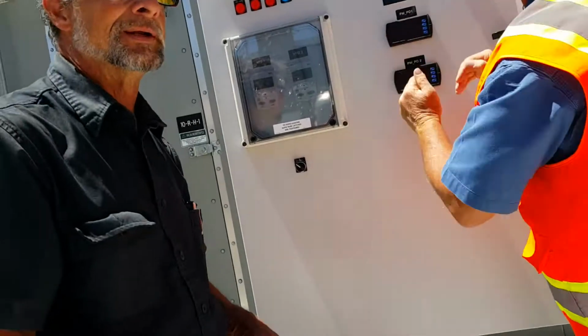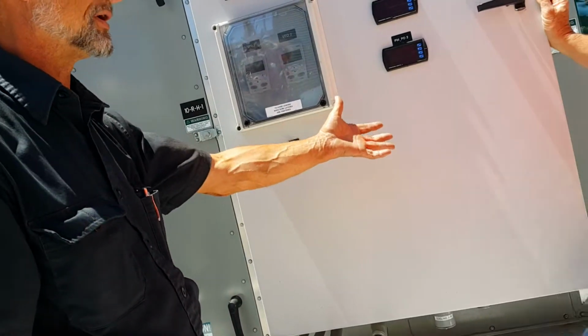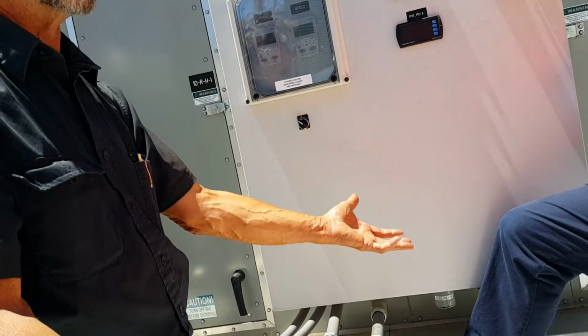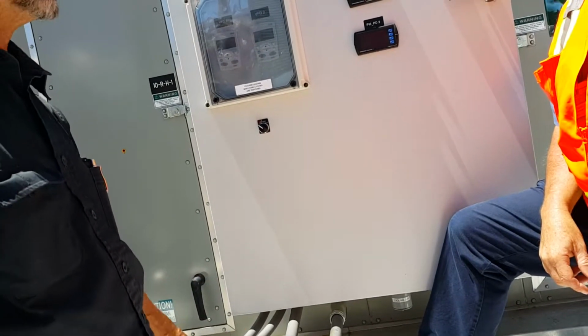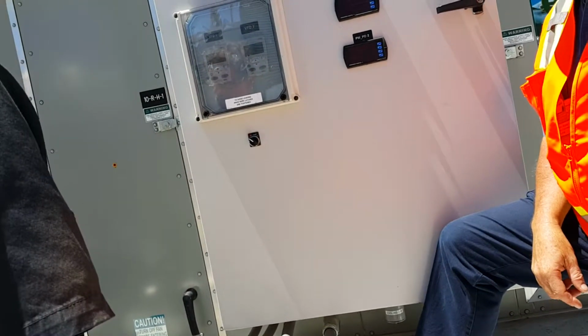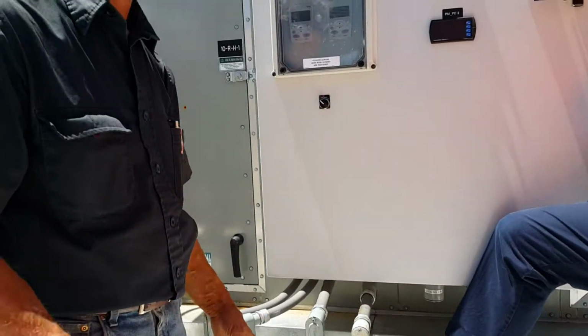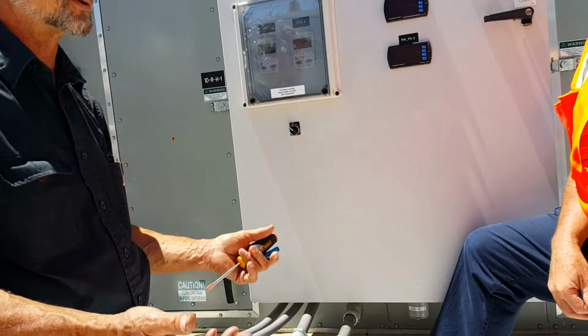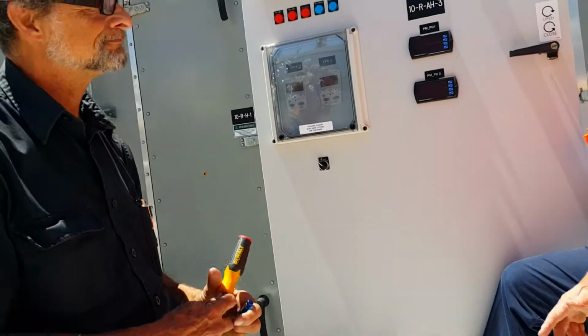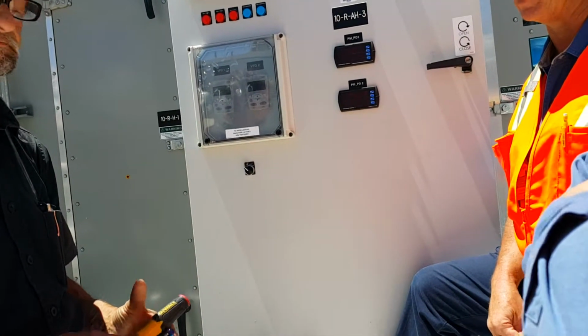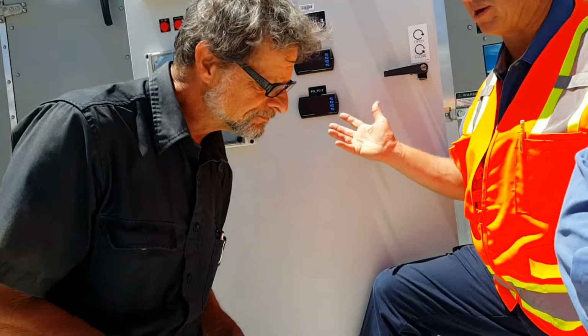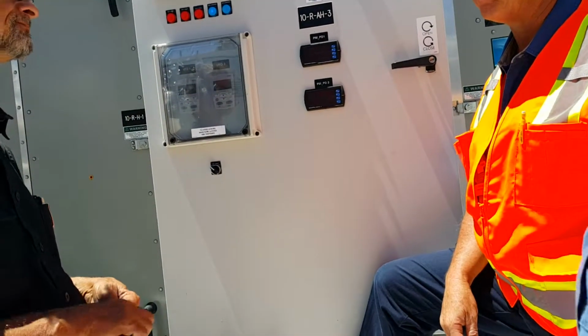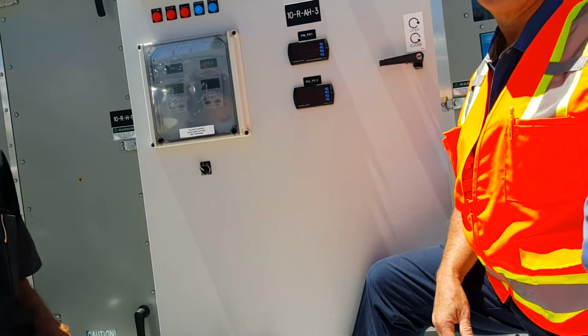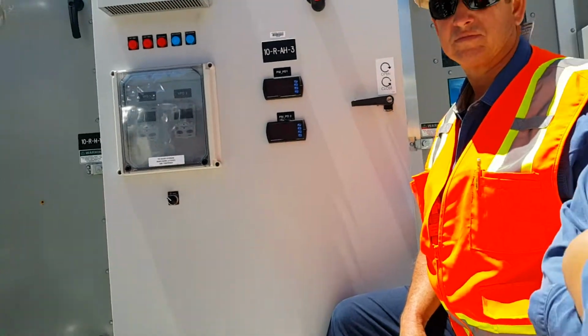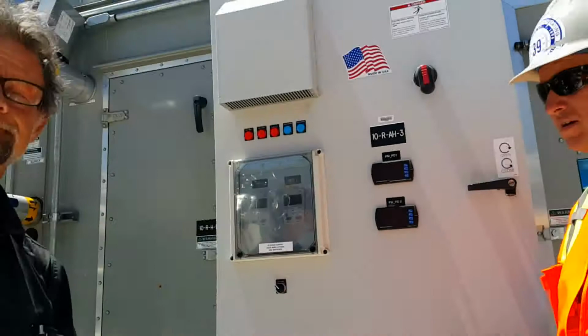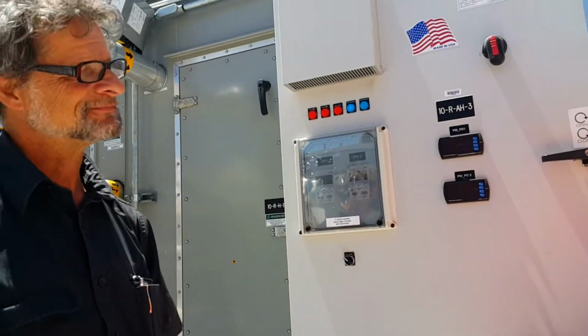So if you want to talk about maintenance, we're really only saying that with the fans you can't grease them, and there are no belts. All you do is look at them. Over here, you clean your condensate pan and change your filters, and there's not much else to do on it. Wait, there's no cleaning belts? No belts. Filters. Direct, sorry. Coils don't need to be cleaned as long as the filters are taken care of, right? And the motor doesn't need greasing. So you don't do anything to them. So we have to have the cleanest pans in town. That's great.